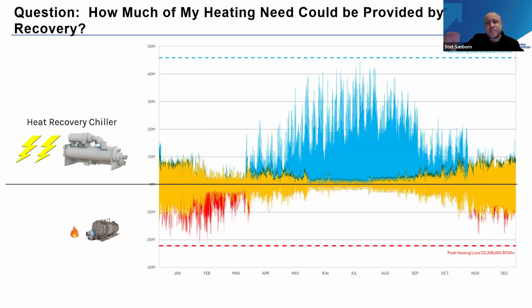And that whole yellow zone are hours where that simultaneous heating and cooling is giving you free heat. So all the folks that are like, oh, my heat pump's not efficient enough, I can't use a heat pump on my project, start focusing on heat recovery chillers or heat recovery heat pumps, because you're going to be getting essentially free heat off of the waste coming from your cooling side, which can offset a tremendous number of hours of heating load. And so notice the area that's left in red is really small. That might be able to be picked up with your existing boiler, a tiny little pony boiler, or, in the next option, a very small heat pump. So next slide.